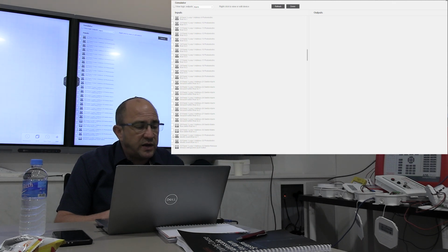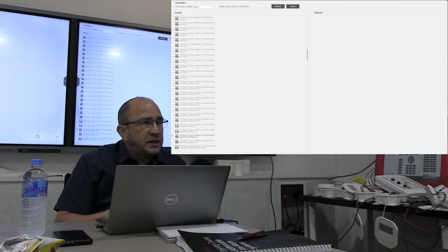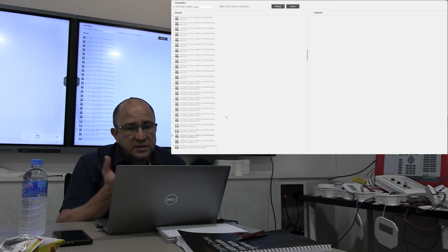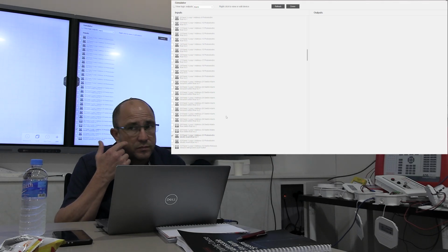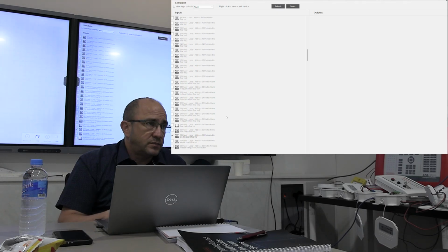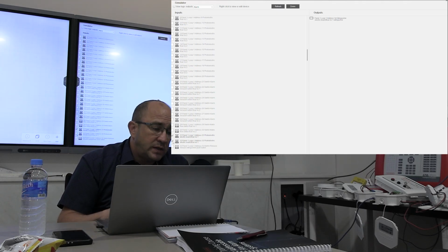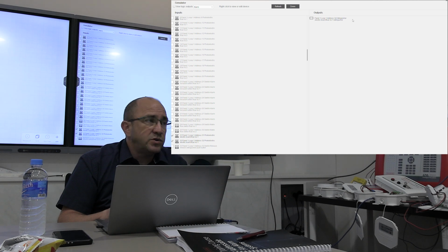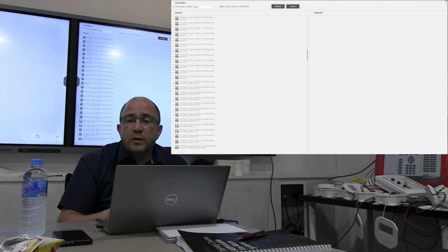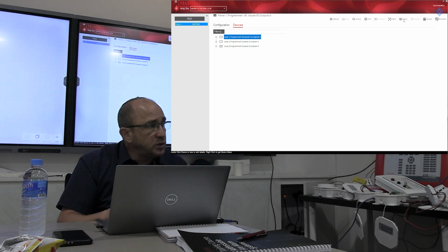Now, what will happen if I activate one detector? Nothing. Why? The electrical board, the extinguisher. Why does one detector do nothing? They need to detect. They need 2 detectors. Here's the other one. Here you are. Electrical board, extinguisher activated. One alarm still has to send the signal and then ring the bell. We didn't program it, but since you want to program it so much, we'll do it. Here you are.